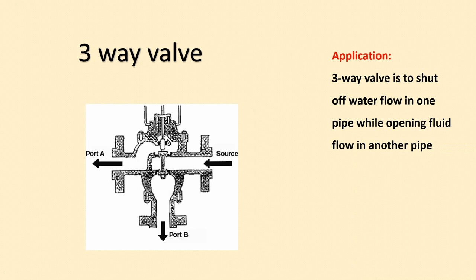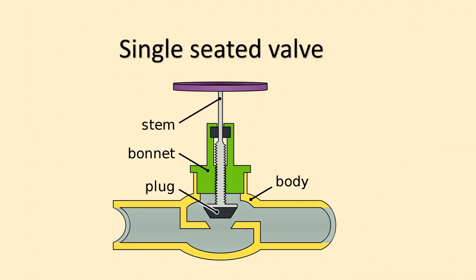Next is the three-way valve. From the figure you can see there is a single source inlet from the right side and two ports — port A and port B. The three-way valve shuts off flow in one pipe while opening flow in another. The process fluid entering the valve either goes into port A while port B is closed, or goes into port B while port A is isolated. That is the main function of a three-way valve.